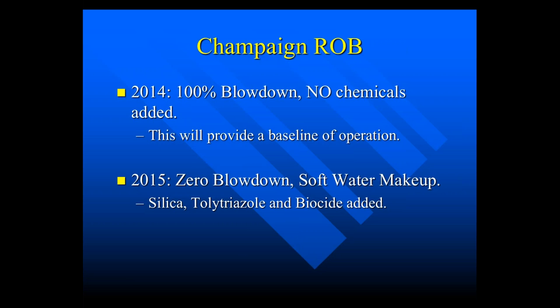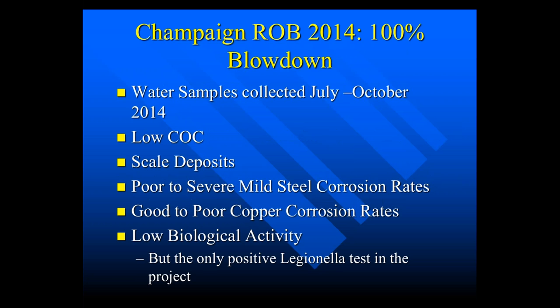In 2015 we instituted the zero blowdown soft water makeup, where we added silica, tolytriazole, and biocide. Looking at 2014 at the Champaign Regional Office Building under 100% blowdown: water samples were collected July to October. It had low cycles of concentration, scale deposits, mild steel corrosion rates that were poor to severe, copper corrosion rates that were good to poor, and low biological activity — but it had the only positive Legionella test of the whole study.